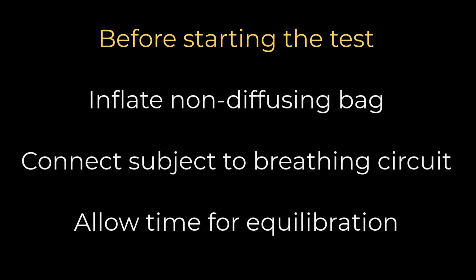With BreezeSuite and Ascent, inflate the non-diffusion bag and connect the subject to the breathing circuit before starting the test. Have the subject breathe the desired FiO2 and allow time for subject adjustment. If you do not allow for equilibration, data may not collect or inaccurate values may be reported. Once the subject has stabilized, select Start and perform the exercise test.